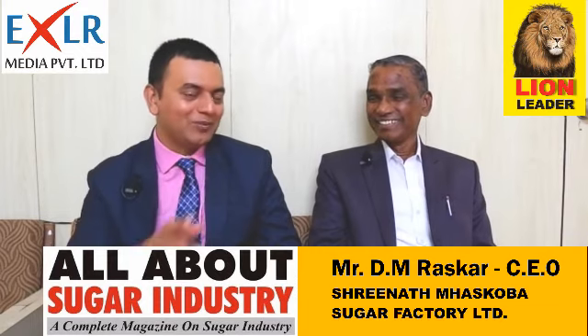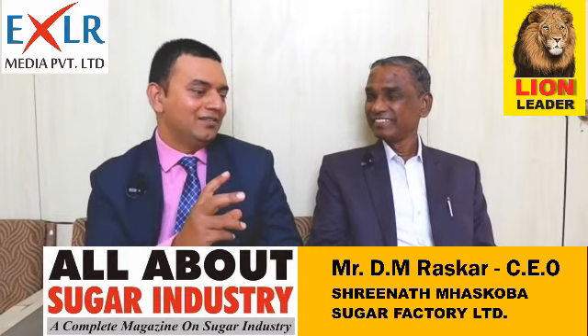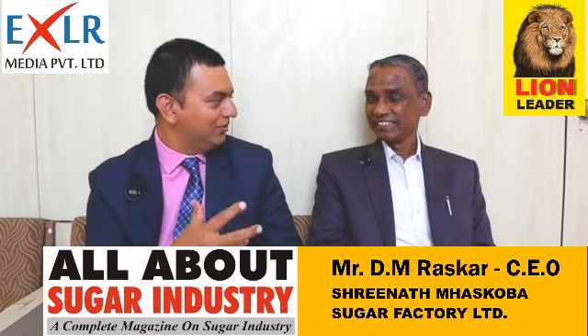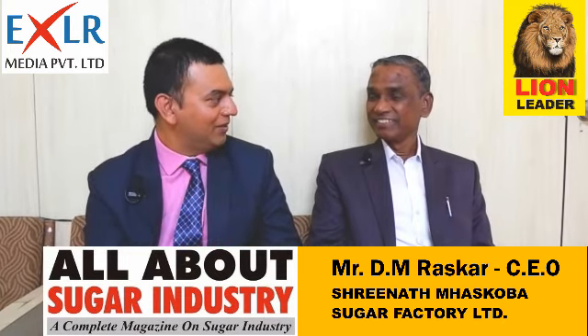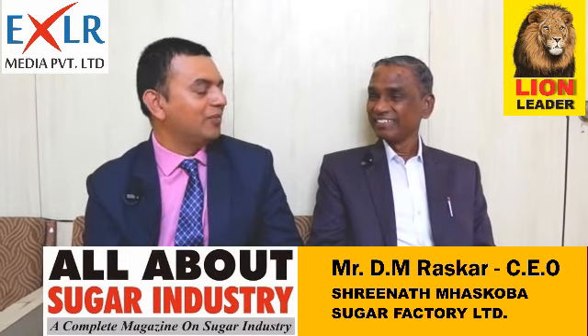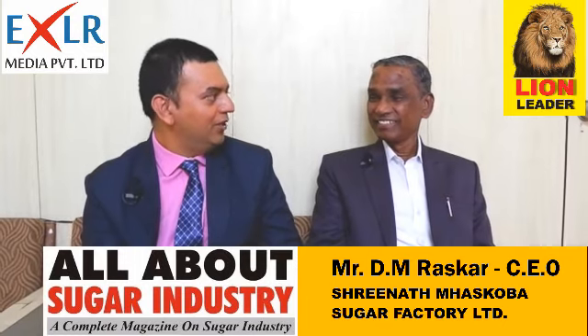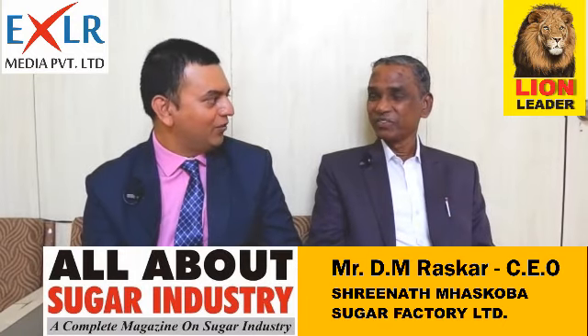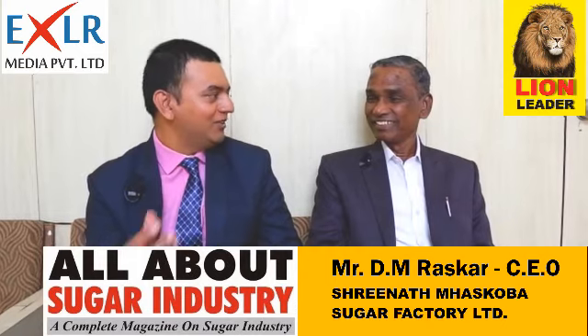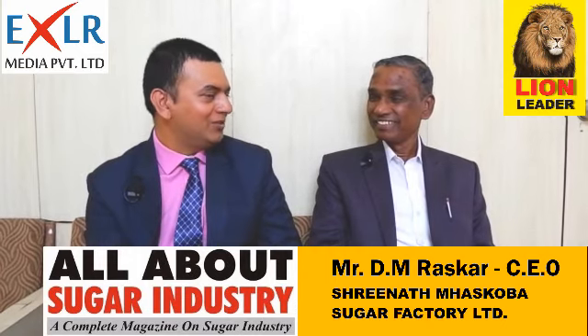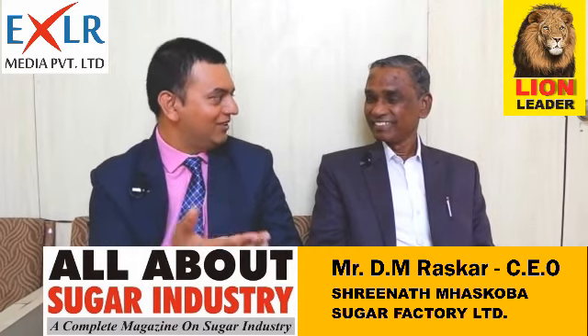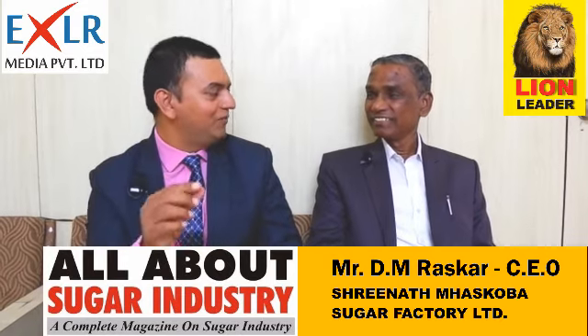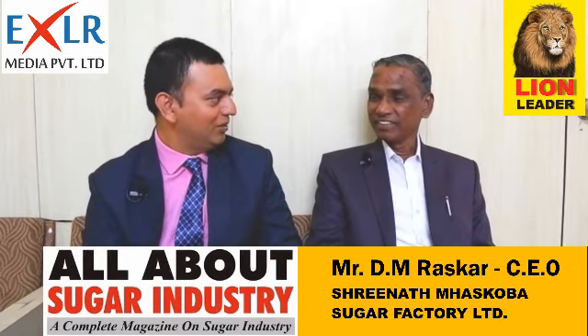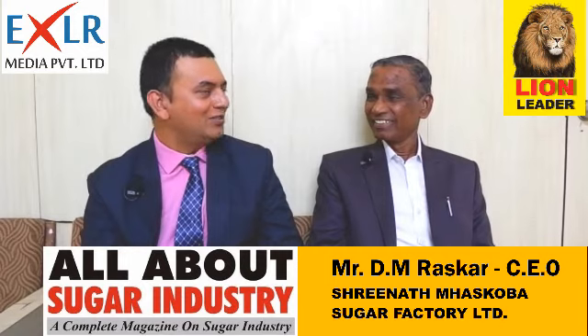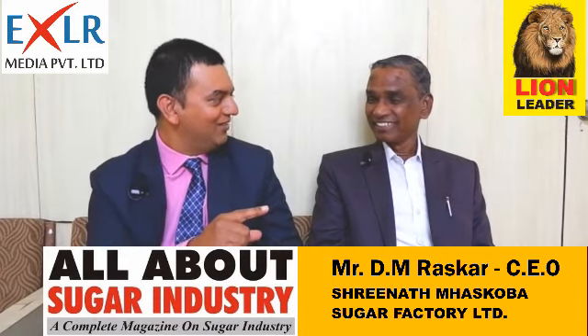Right, now what was the science actually? Because for cogeneration, when you want to install a cogeneration plant, the thumb rule says that for 1 megawatt you need around 5 crore rupees. And you wanted to install a 10 megawatt plant here. Yes, so according to that system, you should be requiring 50 crores from the bank. Right, and so how did you do it in 16 crores, sir?